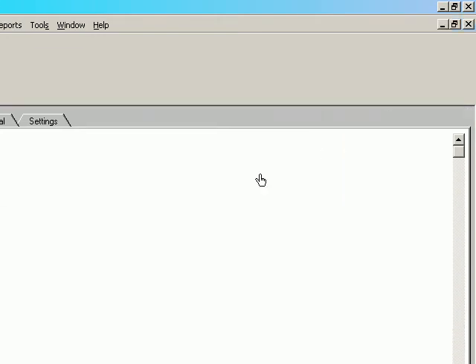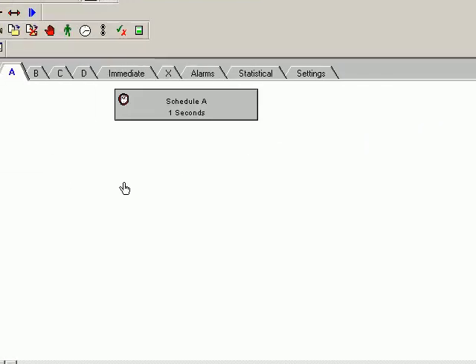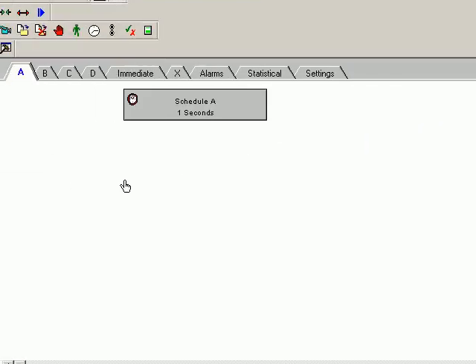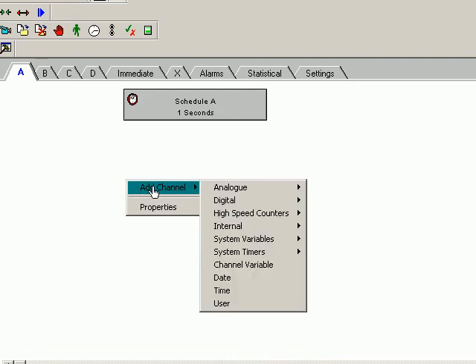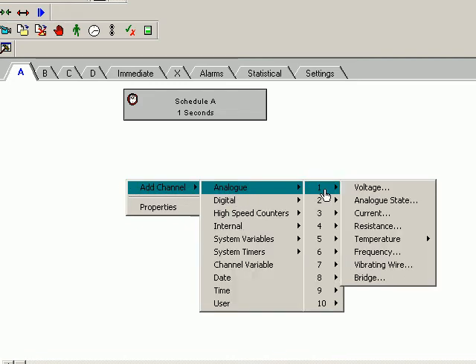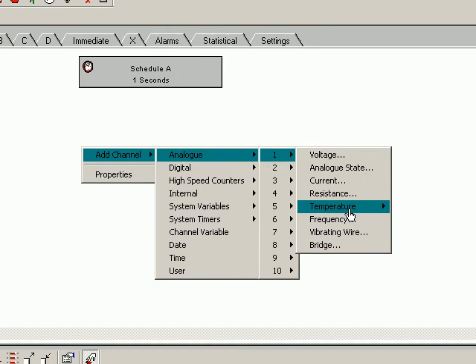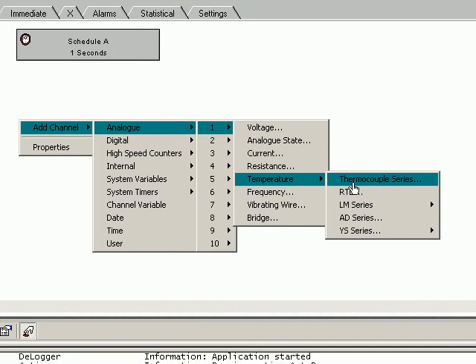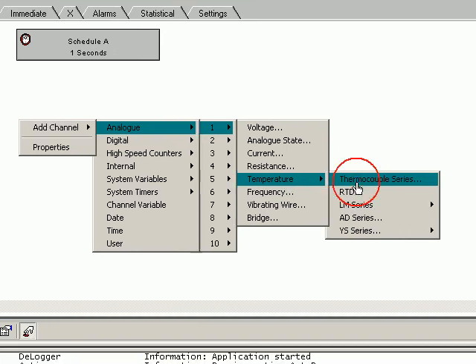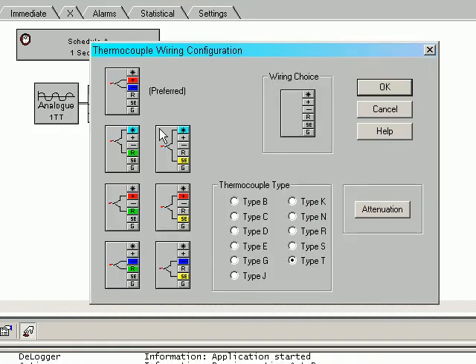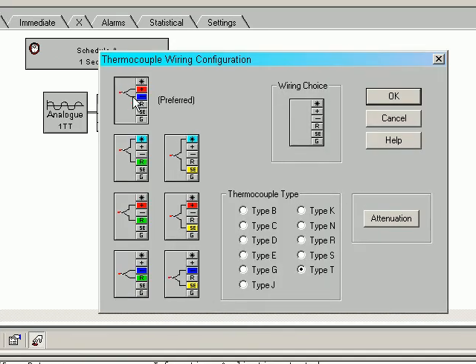I'm going to maximize this window to make it easier to work with. I now right-click, select Add Channel, Analog, Channel 1, Temperature, Thermocouple Series. That's how we've wired it between the plus and the minus, and it's a type T.